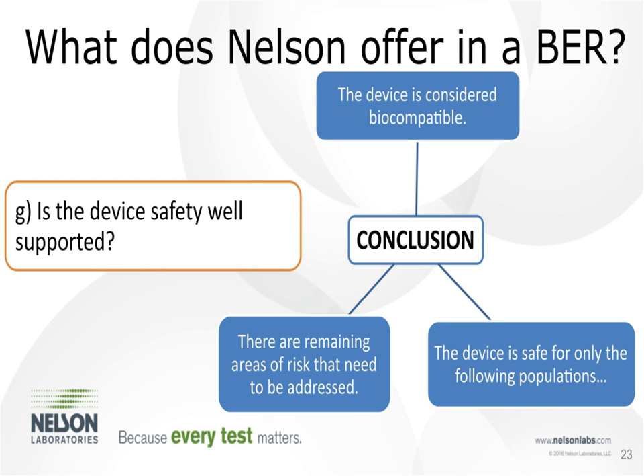At the end, we make the final conclusion. Examples include: the device is considered biocompatible — the end goal we're all hoping for — or there are remaining areas of risk that need to be addressed, or the device is safe only for specific populations. This last conclusion would come through a toxicological risk assessment, as Dr. Campbell discussed yesterday, where threshold levels are based on body weight and safety margins. If the compound is not safe for pediatric or neonatal populations, that would also be identified here. It's beneficial to reference your risk assessment and all testing to give a final conclusion, rather than leaving reviewers to find that information in individual reports.